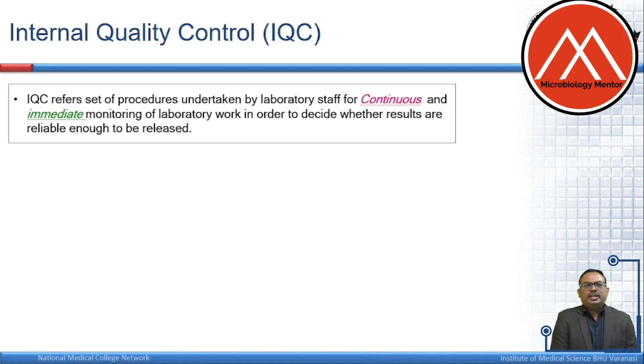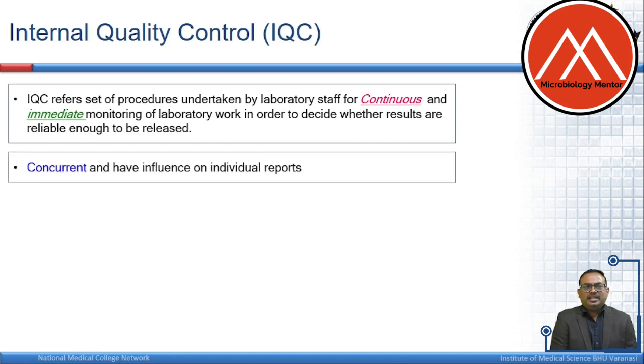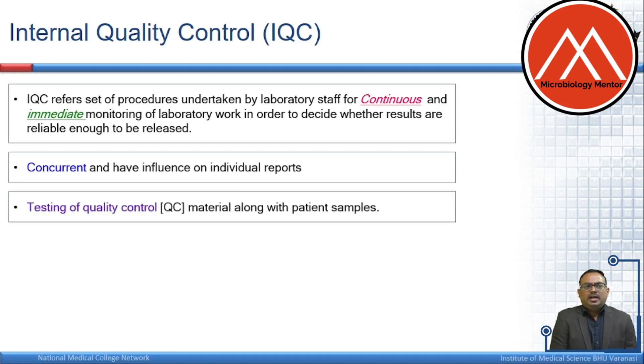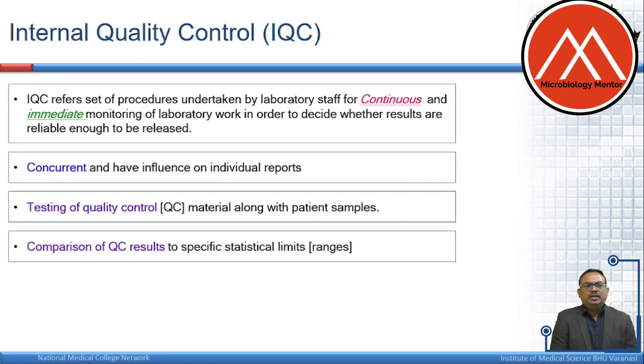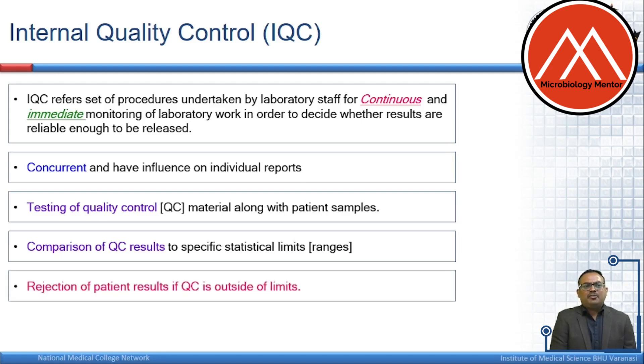Internal quality control refers to the set of procedures undertaken by laboratory staff for continuous and immediate monitoring of lab work in order to decide whether results are reliable enough to be released. It is concurrent and has influence on individual reports, involving testing of quality control material alongside patient specimens. It comprises comparison of quality control results to specific acceptable limits or ranges, as well as rejection of patient results if quality control is outside the limit.